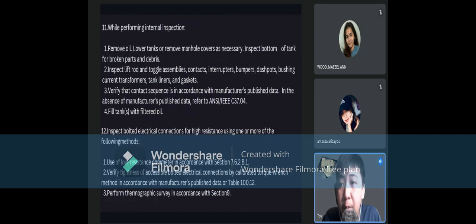11. While performing internal inspection, 11.1: Remove oil, lower tanks, or remove manhole covers as necessary. Inspect the bottom of the tank for broken parts and debris. Ito yung sinasabi na internal inspection, which is ido-drain yung oil, then titignan kung may debris na galing sa iba't ibang machineries na na-impact dun sa loob ng tank or may leak.